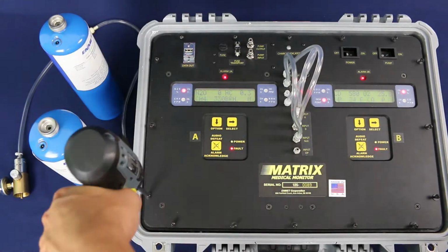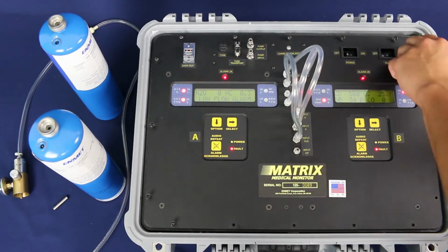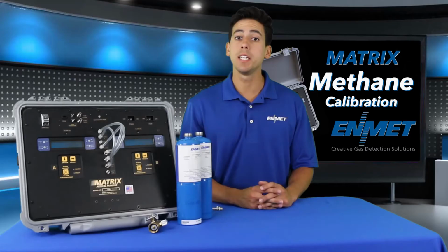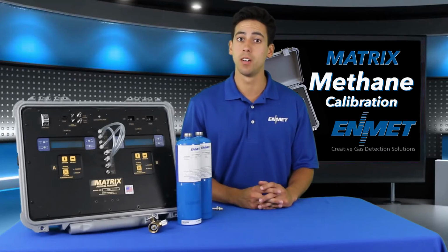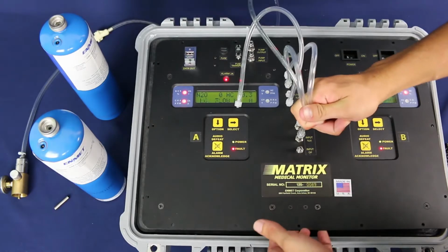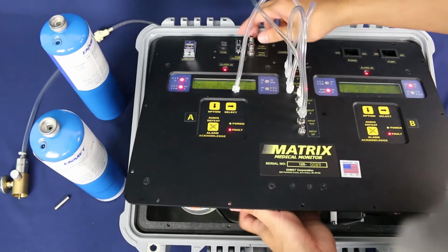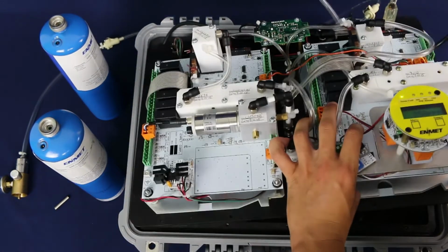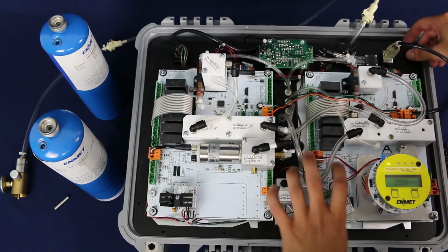We will remove the dew point line because at this time it is an inconvenience to us for flipping over the board to get to the internal sensor transmitter. Now you may lift the panel up and flip it over to access the transmitter. When flipping over the panel, you need to keep the air line attached.